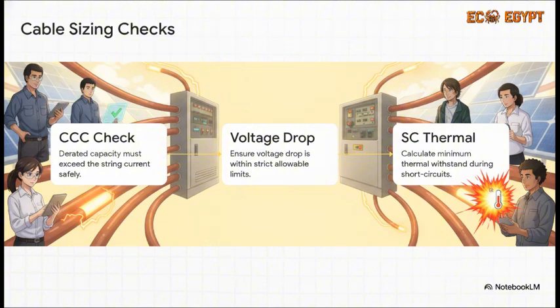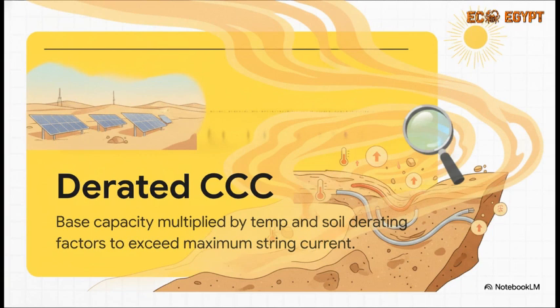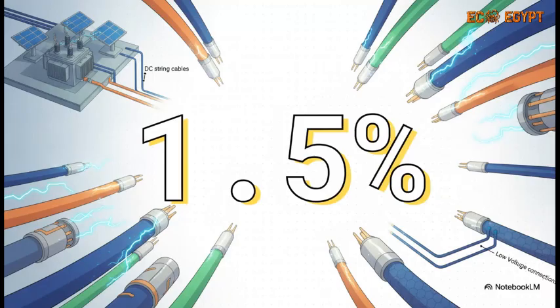massive electrical fire. I actually love this first concept, derating the current carrying capacity, or CCC. You know, out in these blistering hot desert environments where ambient temps can easily hit 40 or 50 degrees Celsius, a cable's raw out-of-the-box capacity drops dramatically. You absolutely cannot rely on standard factory specs out there. You have to mathematically derate it. This means applying very specific reduction factors for things like the ambient temperature, how tightly the cables are grouped together, and the thermal resistivity of the soil itself. It's the only way to ensure your cable survives the harsh reality of the environment while safely handling the maximum string current. Moving to check number 2, the voltage drop, or VD.